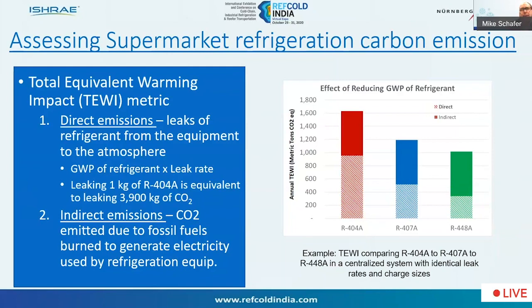On the indirect side, this is a measure of the amount of CO2 emitted due to the fossil fuels that are burned to generate electricity. So that will vary by country. And for this example, looking at the illustration, the effect of reducing the GWP can be visualized comparing 404A, 407A, and 448A. This would be a centralized DX system with identical leak rates and charge sizes. So you can see the contribution of both the direct and indirect emissions.